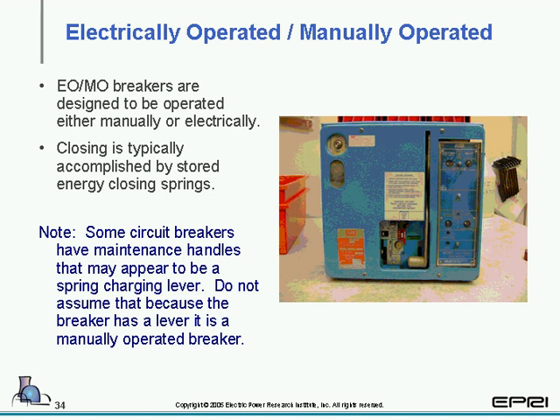Later design breakers may be designed to be operated both electrically and manually, or what are considered EO and MO type breakers. Closing is typically accomplished by stored energy closing springs. And a key note: some breakers may have maintenance handles that appear to be for charging or closing of the breaker, but are not. So it's important to keep that in mind.